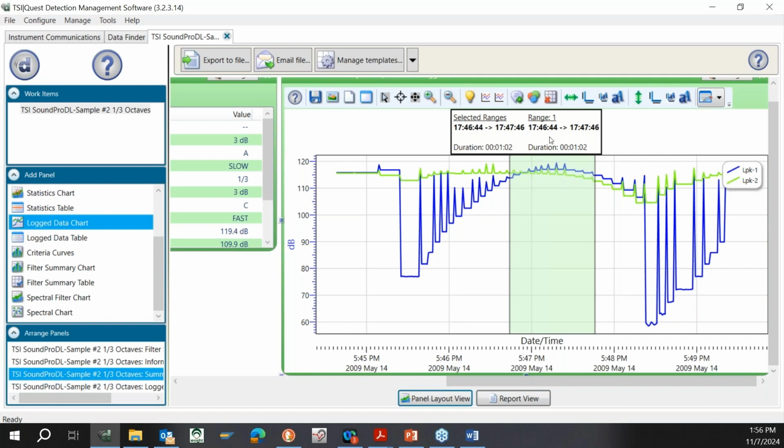Gotcha. Yeah. There is one question. Are there any limitations to a Type 2 sound level meter compared to a Type 1? Yeah, so the limitations of the Type 2 sound level meter would be accuracy. So there are some, and application. So in occupational noise exposure, in 99% of the time, you can get away with the Type 2 sound level meter.